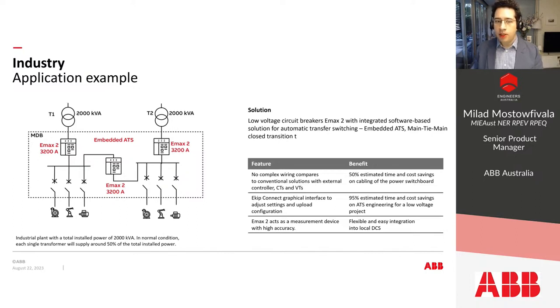This was an industrial application client who was interested in utilizing the embedded circuit breaker function automatic transfer solution, and they were able to utilize the main tie main function here with the use of 3200 amp sized functionalities. This client had a 2000 kVA transformer connection, and the challenge they wanted to resolve was the need to have 50% of total installed power supplied at any time for their plant.